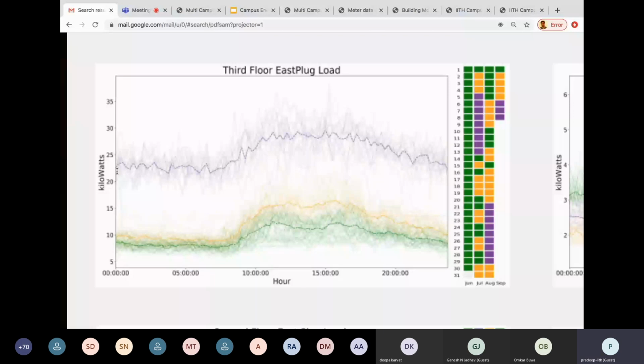Now, which days? If you look at the calendar part here, July 5th to July 13th, only on those days, mysteriously the load increased by about 15 kilowatt throughout the 24 hours. Then after that, the load became a normal pattern again. In the month of August, 21 to August 29, again there is a sudden increase in the load.